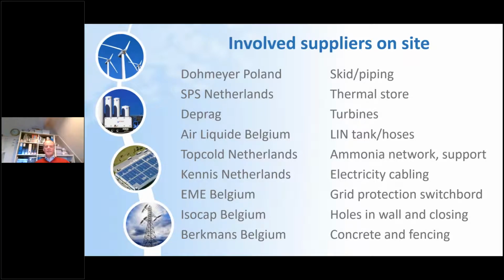We also worked together with Kennis in the Netherlands, who did all the electricity supply and cabling, making it possible to supply current back into the grid. An important part was also delivered by EME in Belgium for the grid protection switchboard. In Belgium, it's not allowed to just put current back into the grid because that can cause disturbances, so to avoid those you need the protection switchboard, supplied by EME in Belgium.